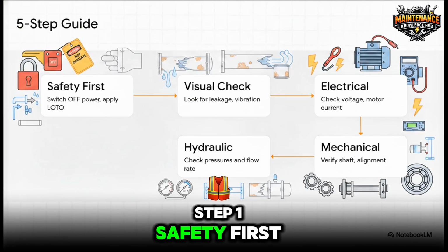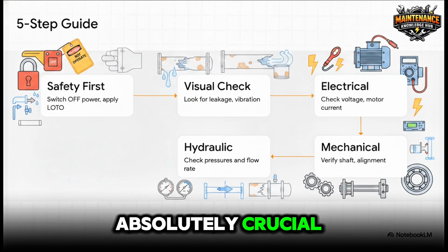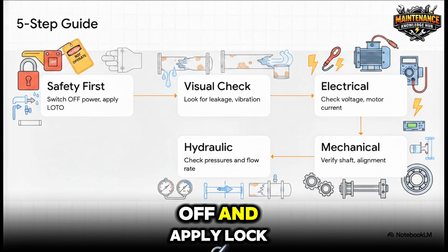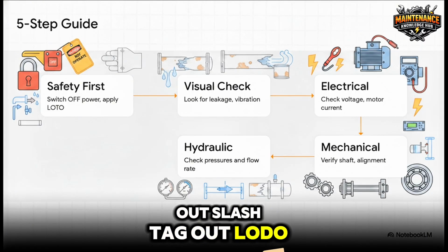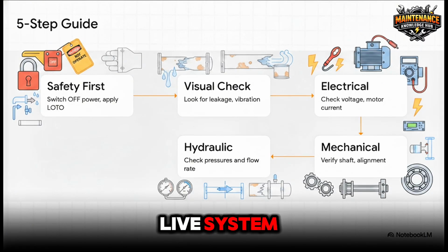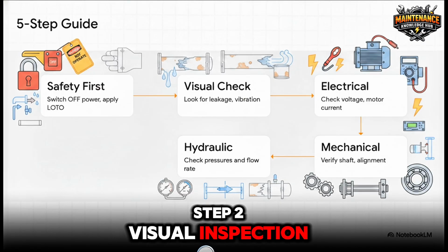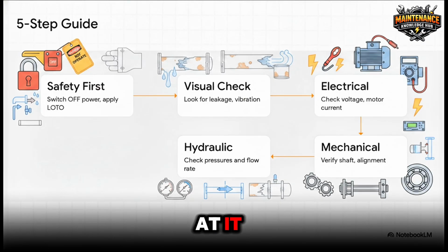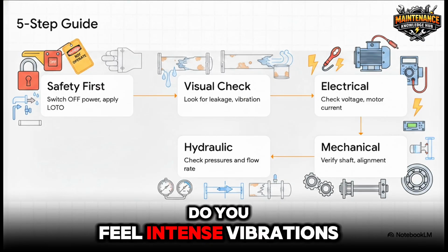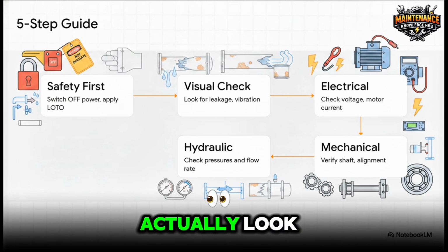Step 1. Safety first. Absolutely crucial. Always switch the power off and apply lockout/tagout LOTO. Never ever touch a live system. Step 2. Visual inspection. Just step back and look at it. Do you see leakage? Do you feel intense vibrations? How does the piping actually look?